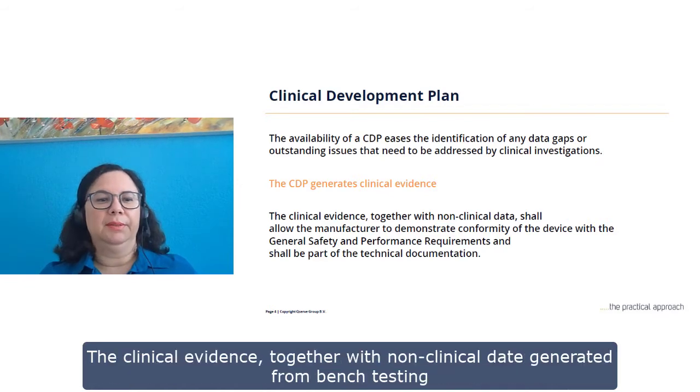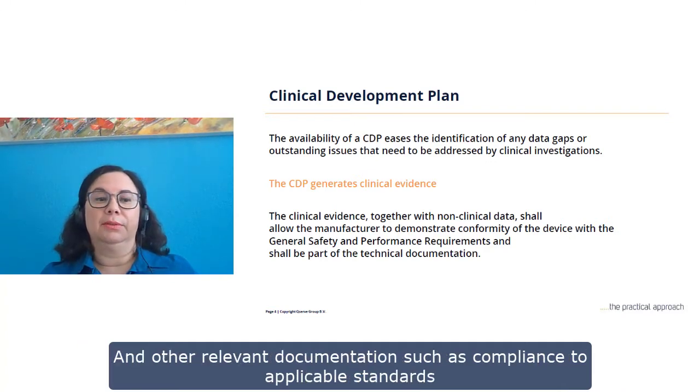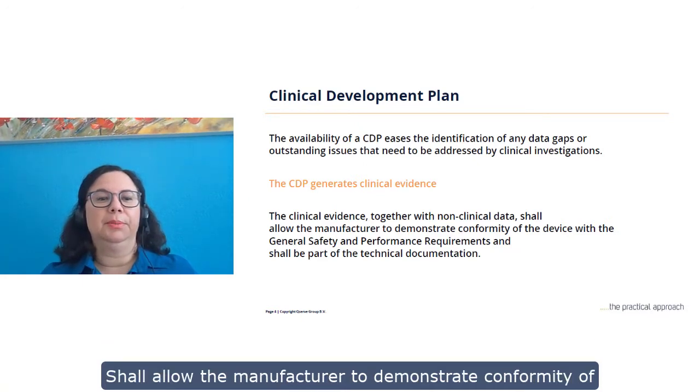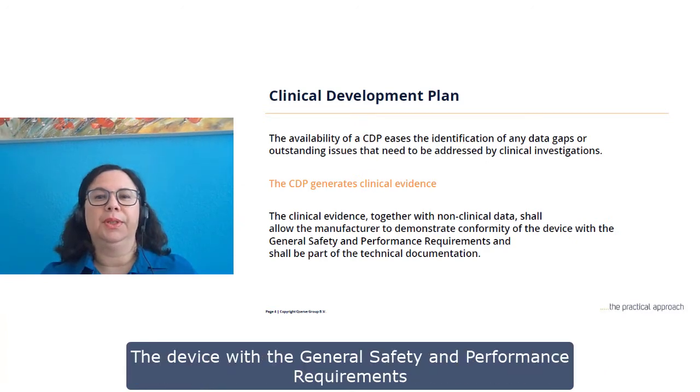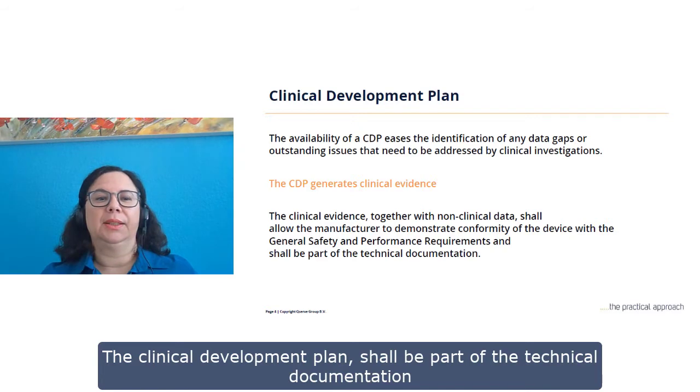The clinical evidence, together with non-clinical data generated from bench testing and other relevant documentation, such as compliance to applicable standards, shall allow the manufacturer to demonstrate conformity of the device with the general safety and performance requirements. The clinical development plan shall be part of the technical documentation.